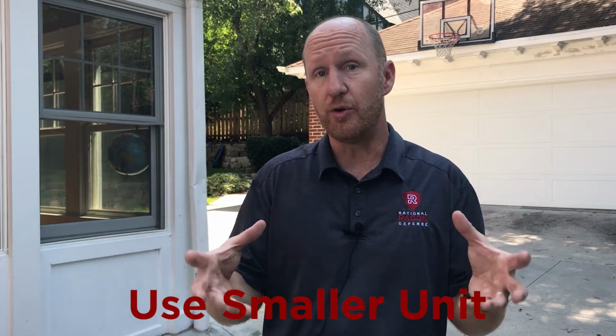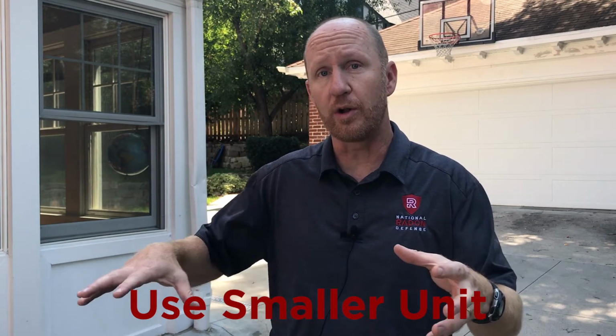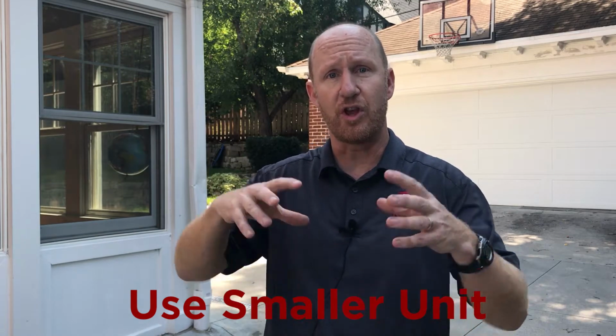And the other great advantage of this is you can use a smaller unit because you're just addressing the lower levels of the home versus addressing the whole home. So you can get away with a smaller unit to address the lower level, which is where the radon is, and also where a lot of the other indoor air quality issues are too. So you can go right at the issue. We're going to walk you through from the beginning to the end of how to install this energy recovery ventilator.